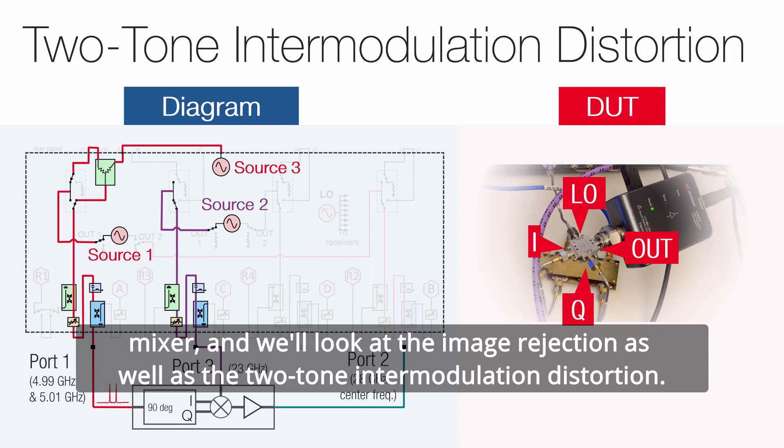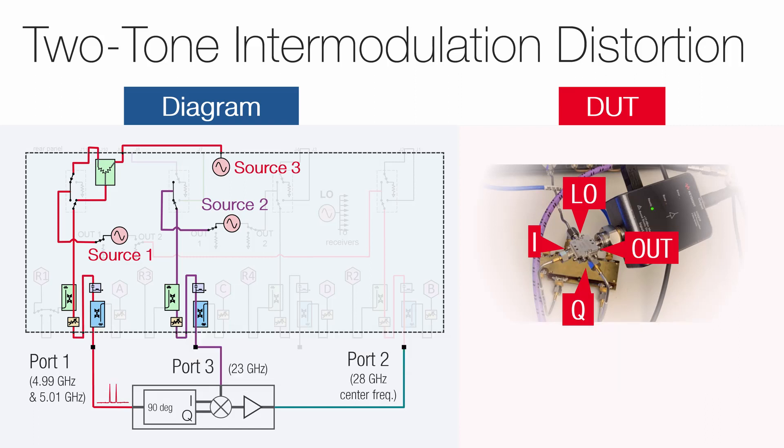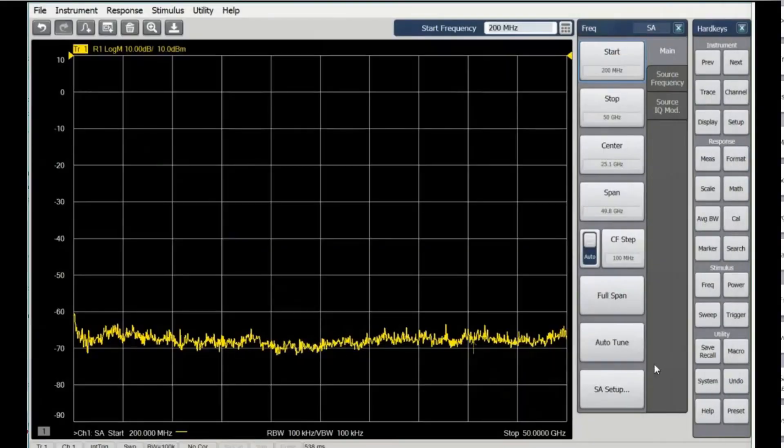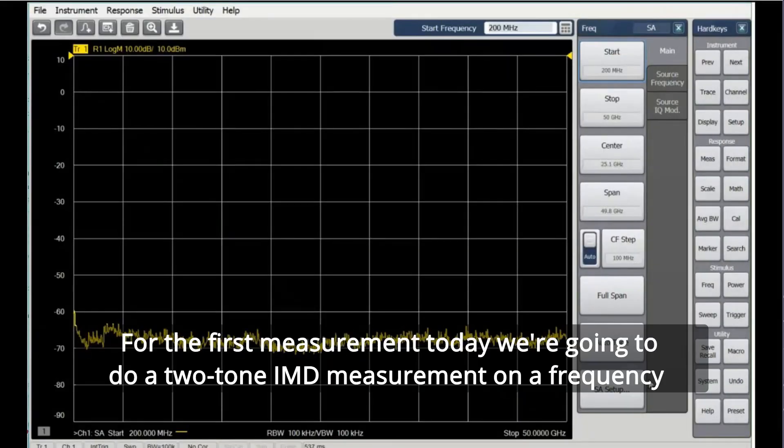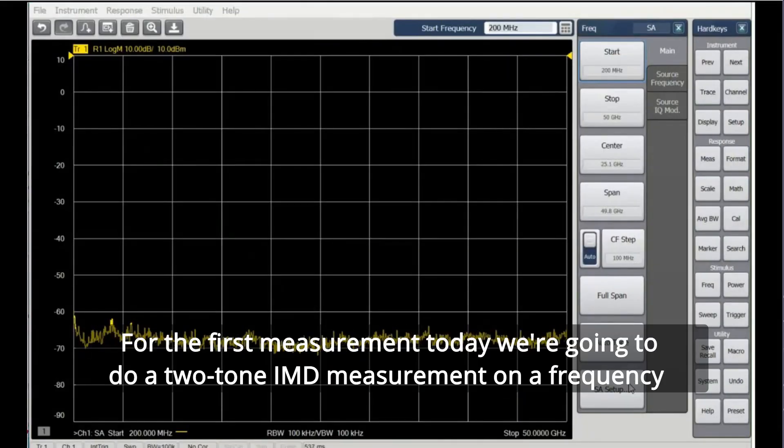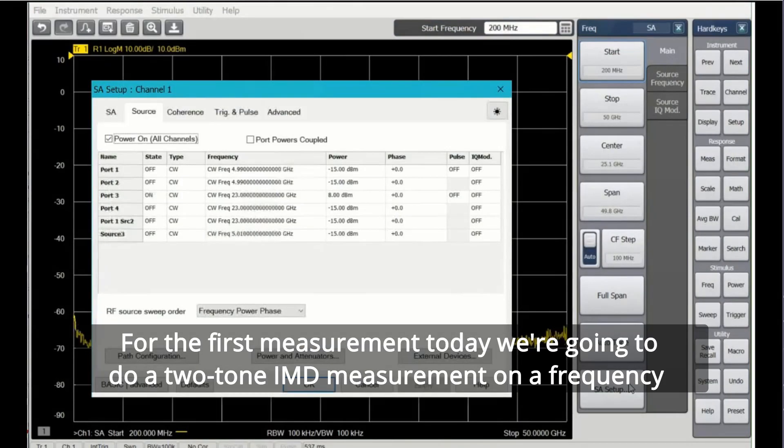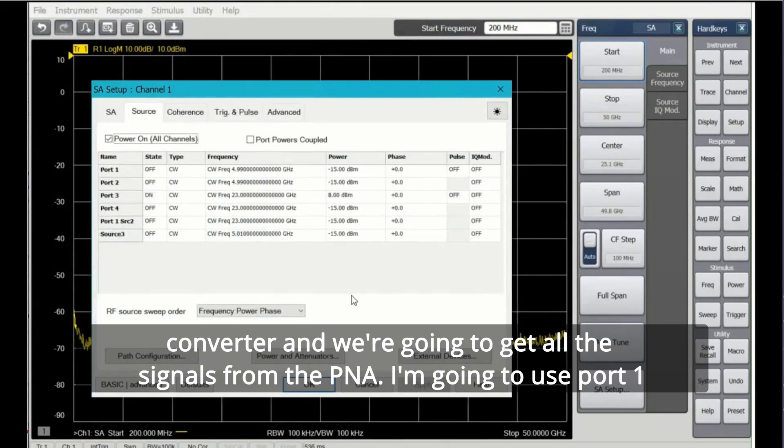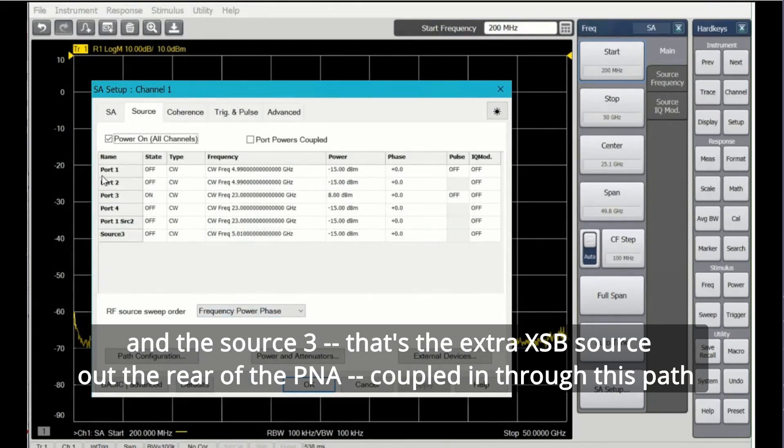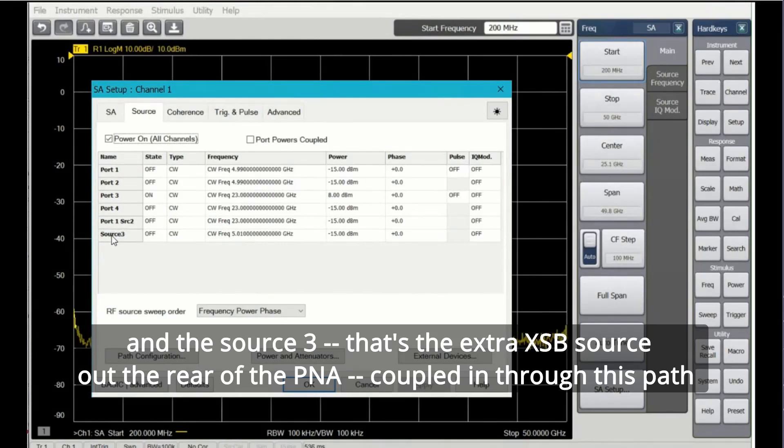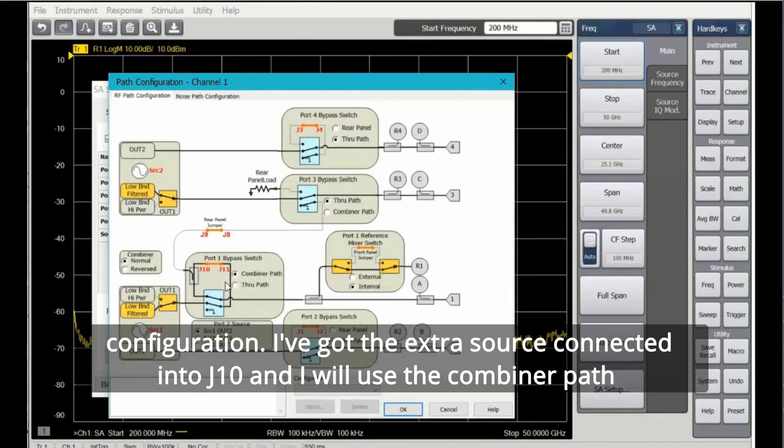For the first measurement today, we're going to do a two-tone IMD measurement on a frequency converter, and we're going to get all the signals from the PNA. I'm going to use port 1 and the source 3, that's the extra XSB source out the rear of the PNA coupled in through this path configuration.